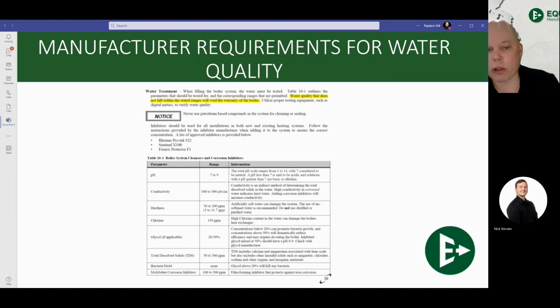The only way to hit a lot of these numbers, well, there's basically only two ways. Number one is to use demineralized water to get your total dissolved solids and your hardness down to where you need them. Also your conductivity. As I mentioned, softened water can add to a higher conductivity. So demineralized water takes care of your TDS, your hardness, and your conductivity, and that leaves you only with your pH to worry about.